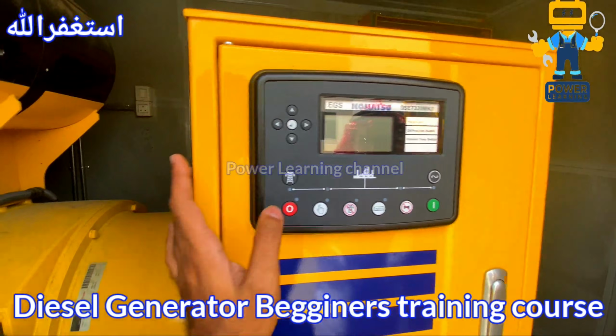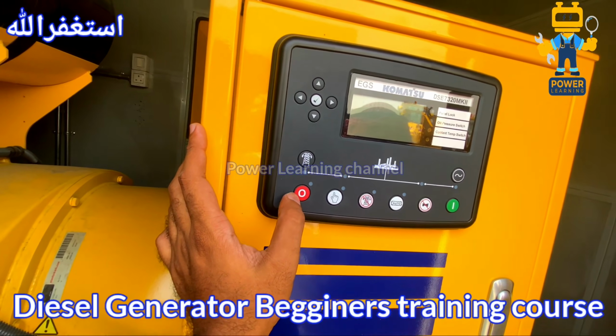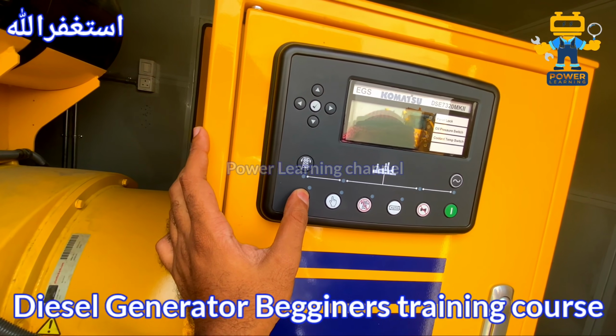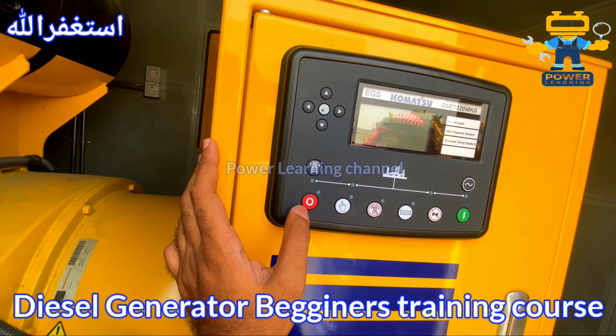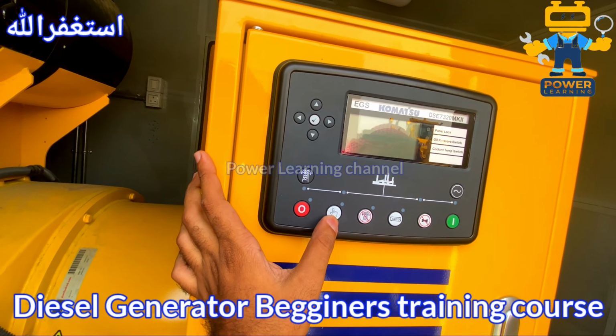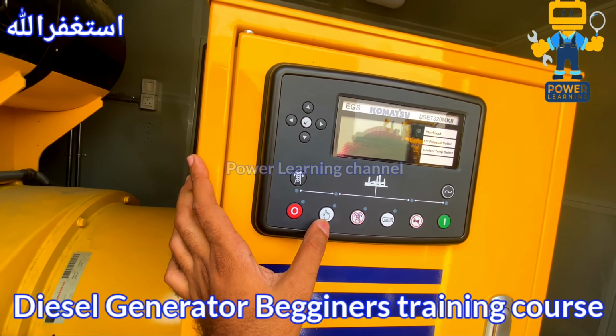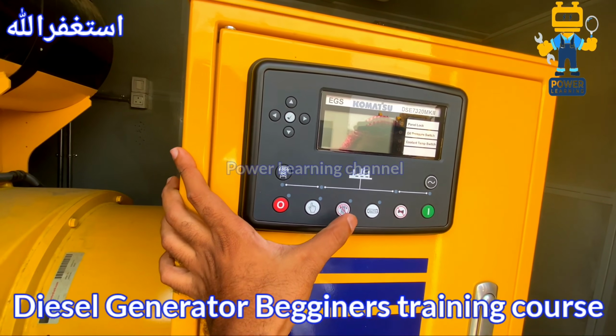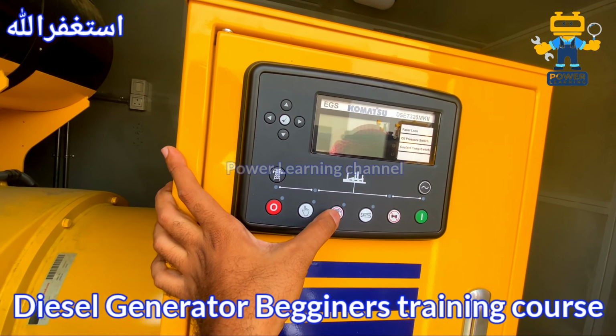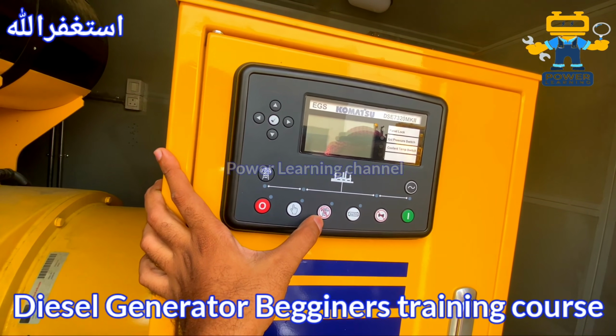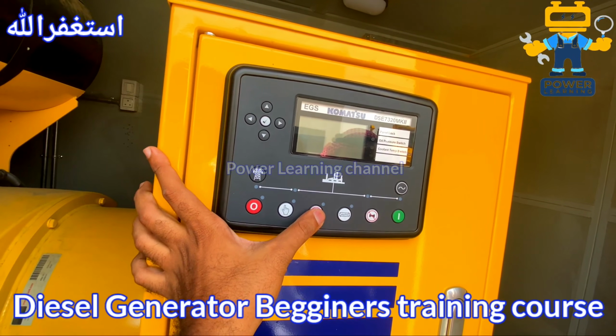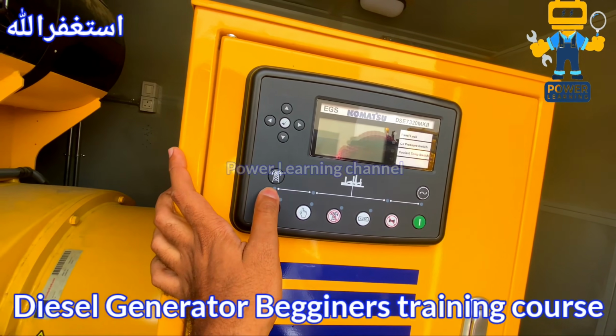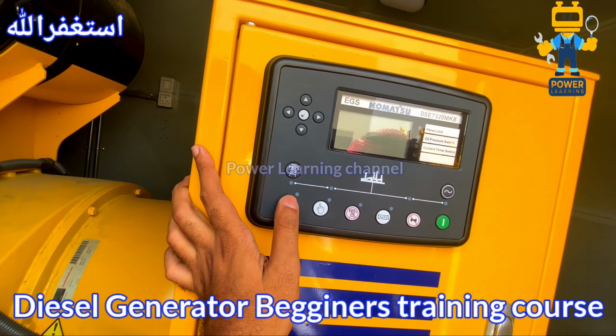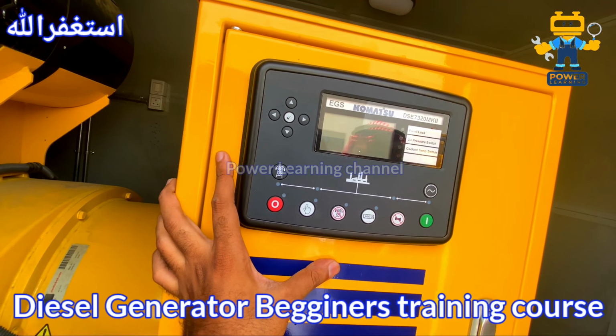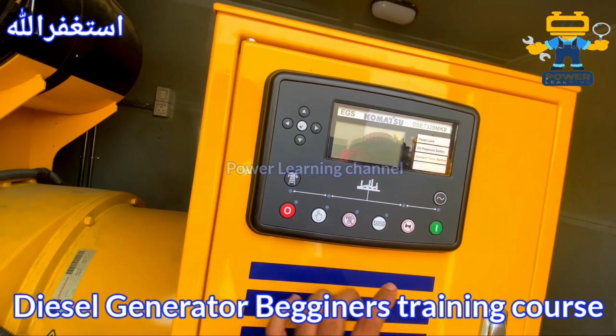This first button is for stop and reset of the alarm. This button we use for manual mode selection. This button is for mains inhibit, like a test button. If we want to test the generator, we just press this, so it will sense that mains has failed, and it will start the generator automatically. This is the test button.